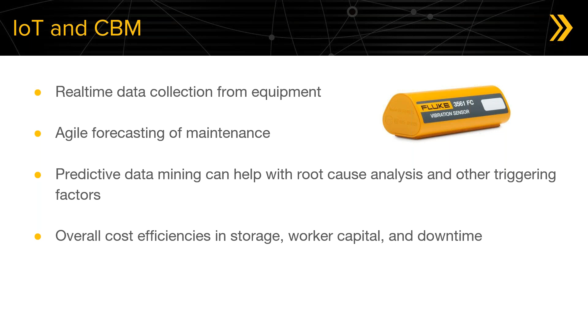So what are the other possible leading indicators of failure that might help us with a CBM strategy? I just talked about vibration, but you're also talking about load, acoustics, temperature, pressure. All of these can be leading indicators of failure. So it's up to us as a maintenance organization to try and identify what those are ahead of time, and then integrate our technology into play with, like I said, SCADA and other forms to enable us to pull information in to work on it.